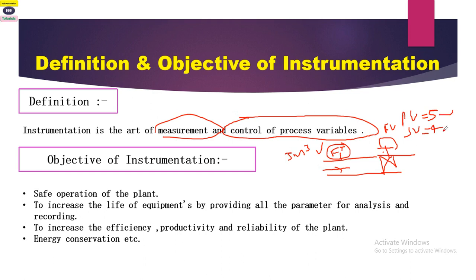Currently the flow is 5 cubic meters per hour and the set point is 4 cubic meters per hour. So the controller will give an output value for closing the valve — the valve will move in the close direction so that the FT value comes to around 4 cubic meters per hour. This is how the FT measures and the controller controls the process variable.